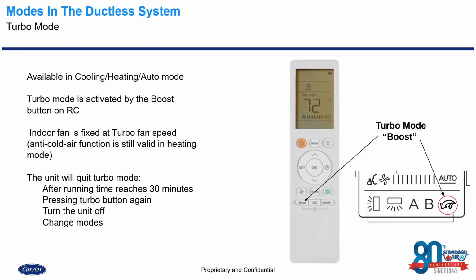Okay, so we know the turbo mode is activated by pressing the boost button on the remote control. That indoor fan is going to be fixed at a high speed, or a turbo fan speed. The compressor is going to be running at full modulation, same thing with the outdoor fan motor. So essentially, whatever set point you pick, whether it be 72, 68, 70, 76, depending on the mode that you're in, the system has 30 minutes to try to reach that set point running in full modulation.